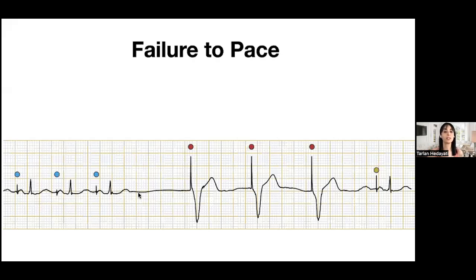And then you can see that something happened here. Now there's no more atrial spikes. So something went wrong with that atrial pacemaker, and it's no longer generating atrial spikes. This is failure to pace of the atrial pacemaker.